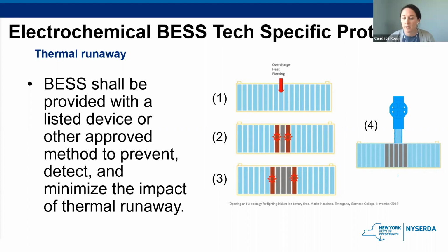So you have here on the screen to the right basically the separate stages. Here you're basically looking at what would be a module. So you might have an overheat or overcharge or piercing of one cell, and the heat and everything starts moving and running away to the next cells. And that is the beginning of a propagation. So you need to make sure you have a device to help prevent, detect, and minimize the impact of thermal runaway.